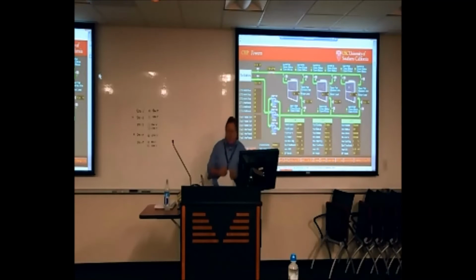And Aaron, you may know this. There was talk, I think, that the stilling wells were almost at the same height as the overflow, so there was talk of maybe cutting an inch or 2 off that overflow pipe. Did that ever happen, do you know, or did that come through on the commissioning report? It did, and we cut a couple inches off, so now it would run off the overflow first before it went outside. Okay. Okay, and I hadn't heard, so given that, I'll drop my level down a little bit, so right now I'm probably at the overflow. I'll drop mine a couple of inches, so I'll catch it before we hit the overflow then.